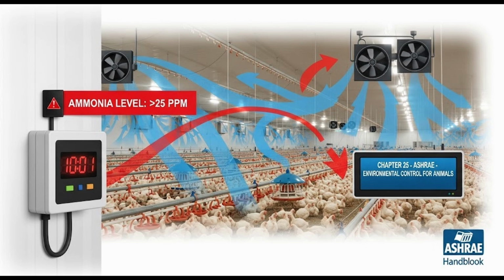Simple as that. And evaporative cooling, like the fan and pad systems. Very common, especially in hot, dry areas. Extremely effective. The handbook provides a quite detailed method to calculate the required airflow for these systems. You start with a base rate, like the 40 L/s per square meter you mentioned. Yes, something like 40 liters per second per square meter of floor area is a typical starting point. But then you modify that base rate using several factors. Factors for what? Things like your site elevation, since air is less dense higher up, the maximum light intensity you expect, and the maximum acceptable temperature rise you can tolerate inside compared to outside. There are tables for these factors, FE, FL, FTT. You multiply them together to get a combined adjustment factor, FH, for the base airflow rate. It's quite specific. Okay, a calculated approach.